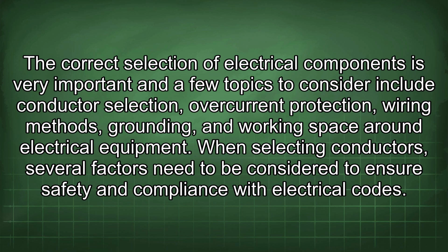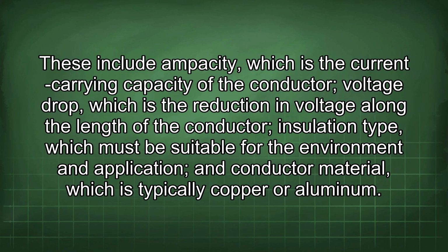When selecting conductors, several factors need to be considered to ensure safety and compliance with electrical codes. These include ampacity, which is the current carrying capacity of the conductor, voltage drop, which is the reduction in voltage along the length of the conductor, insulation type, which must be suitable for the environment and application, and conductor material, which is typically copper or aluminum.